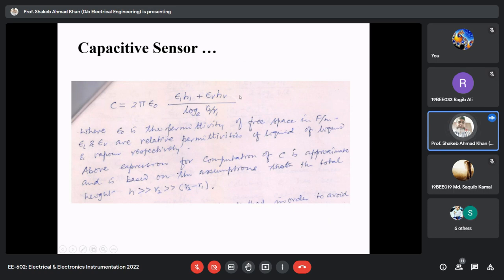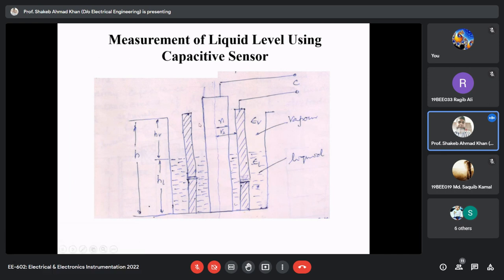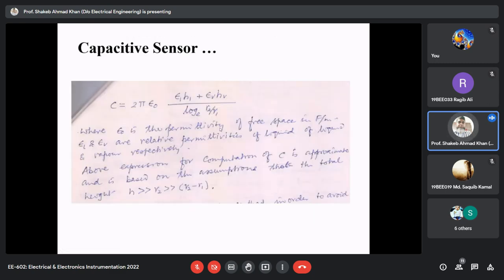You must have studied the capacitance of a cable between sheath and core. The same formula is used here. So the capacitance is equal to liquid permittivity and the liquid height plus vapor, the empty part. Here we are calling it vapor, and then liquid. Vapor means air here. This is the outer electrode radius, and this is the inner electrode radius. This formula came with the assumption that height is much more than the radius, or difference of radius.